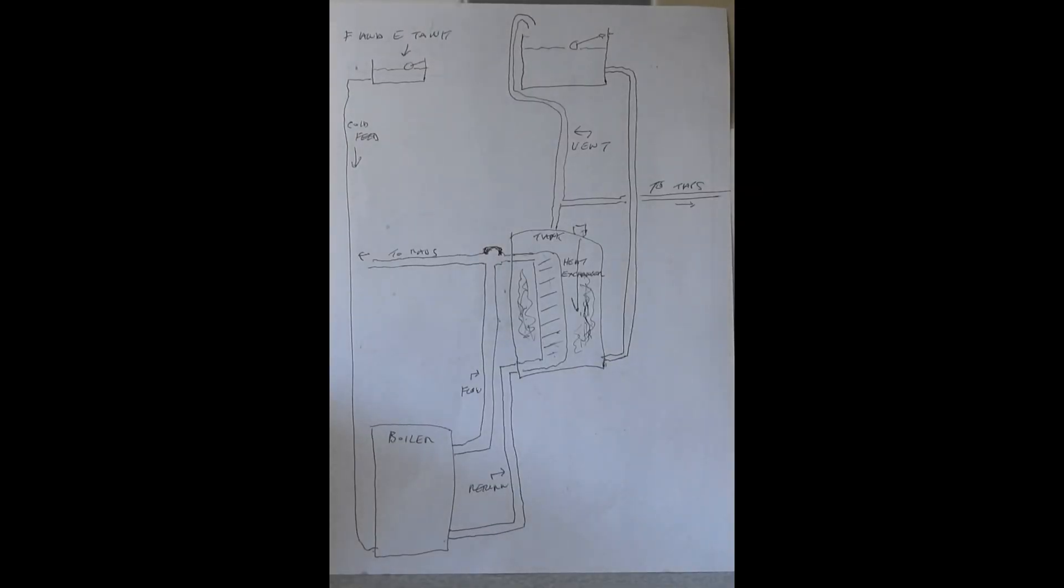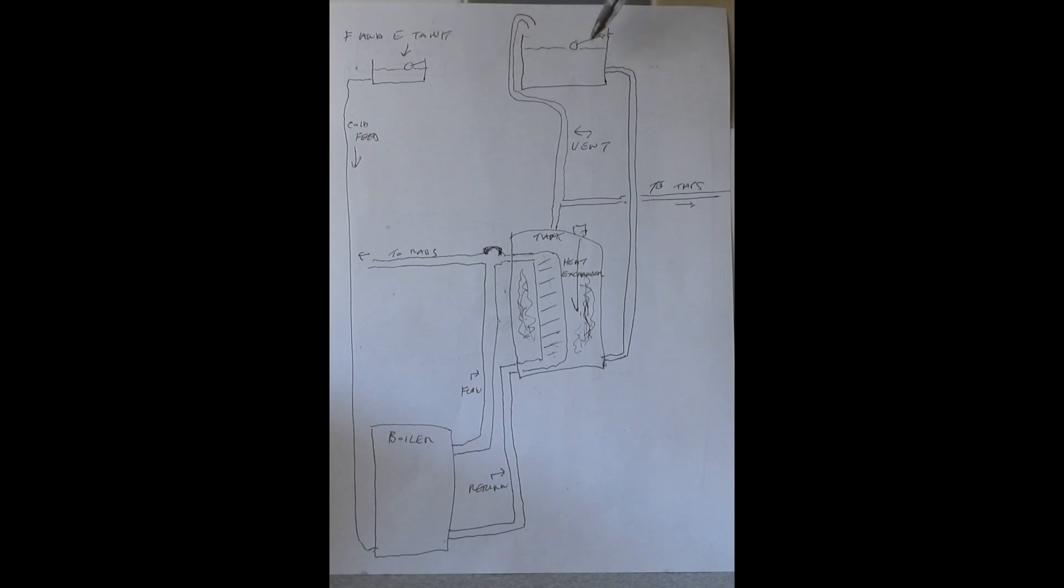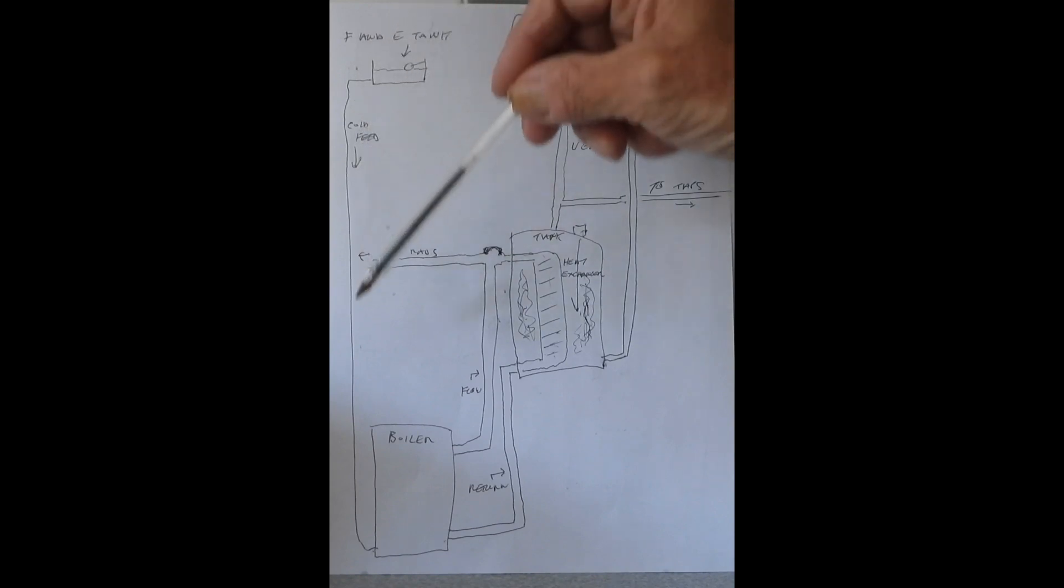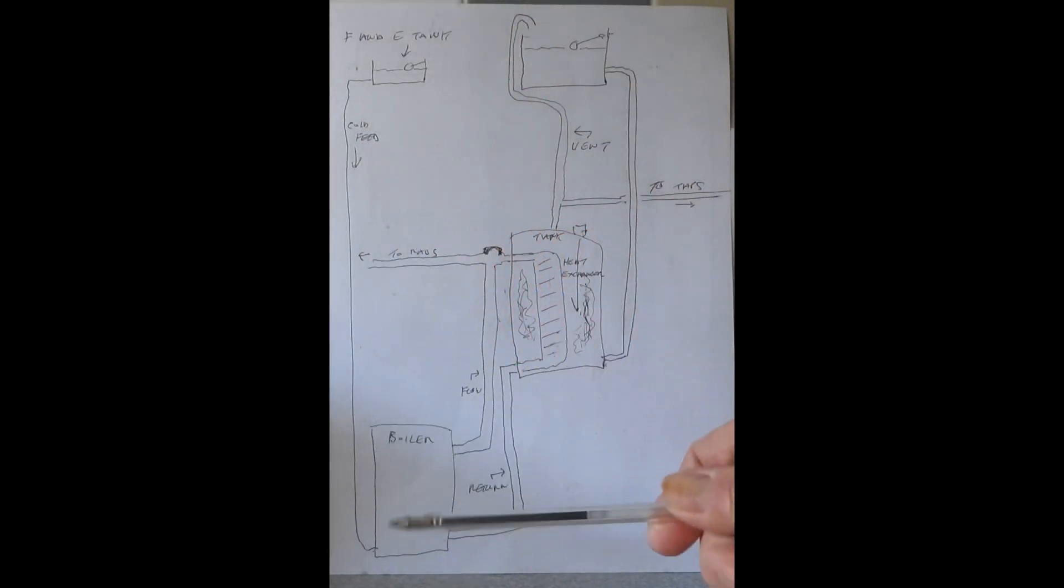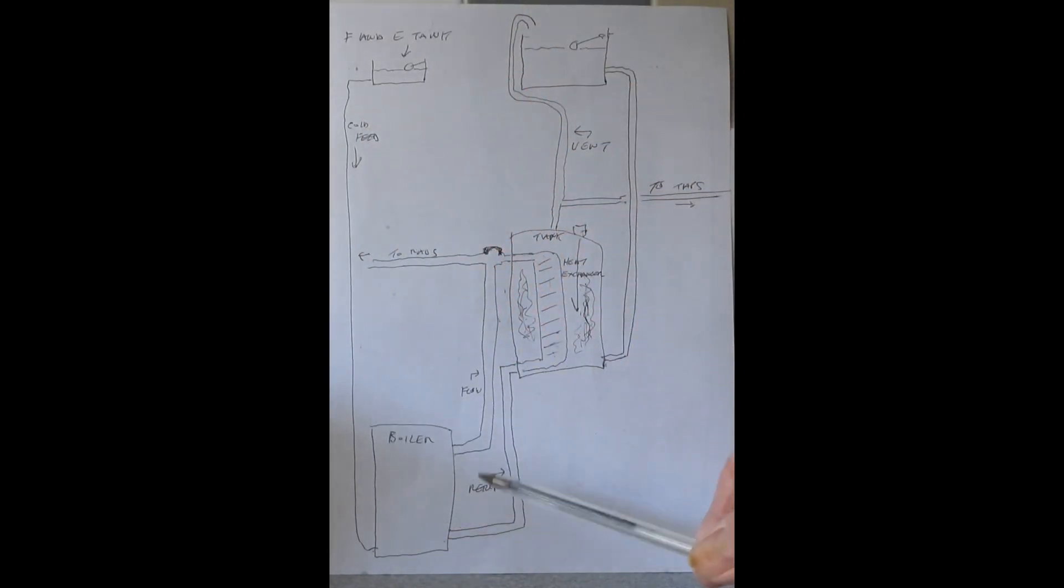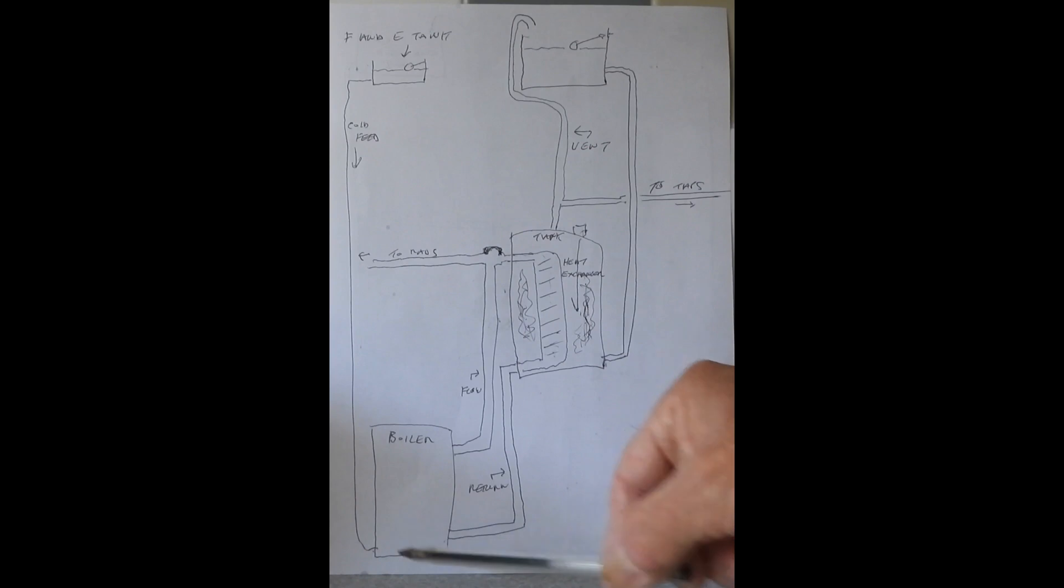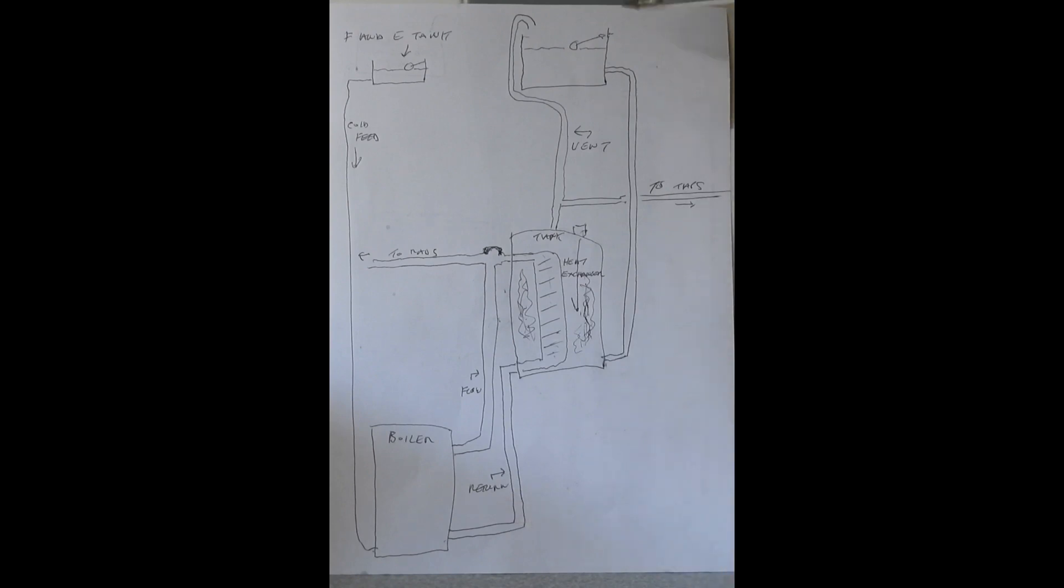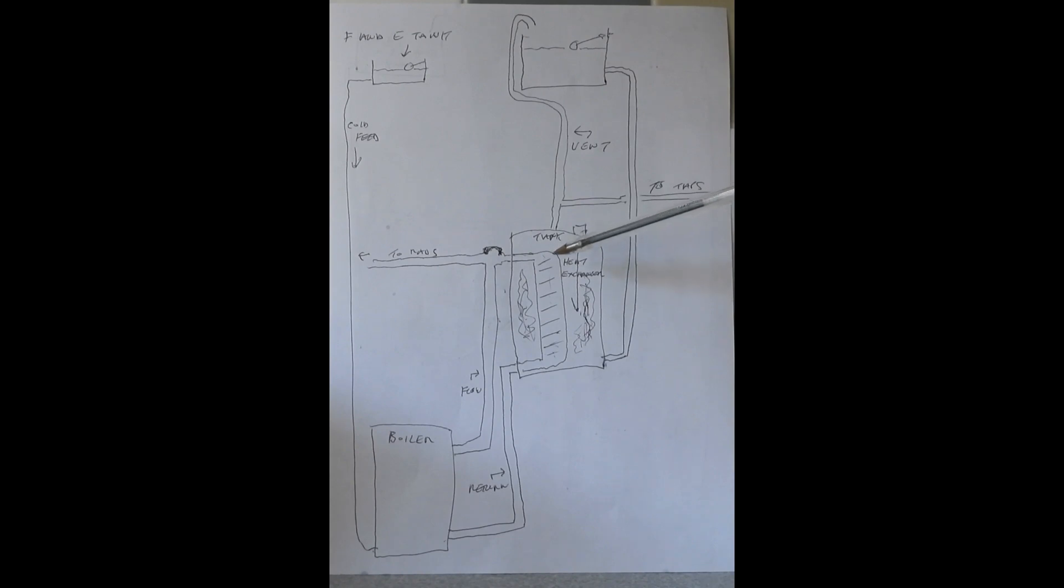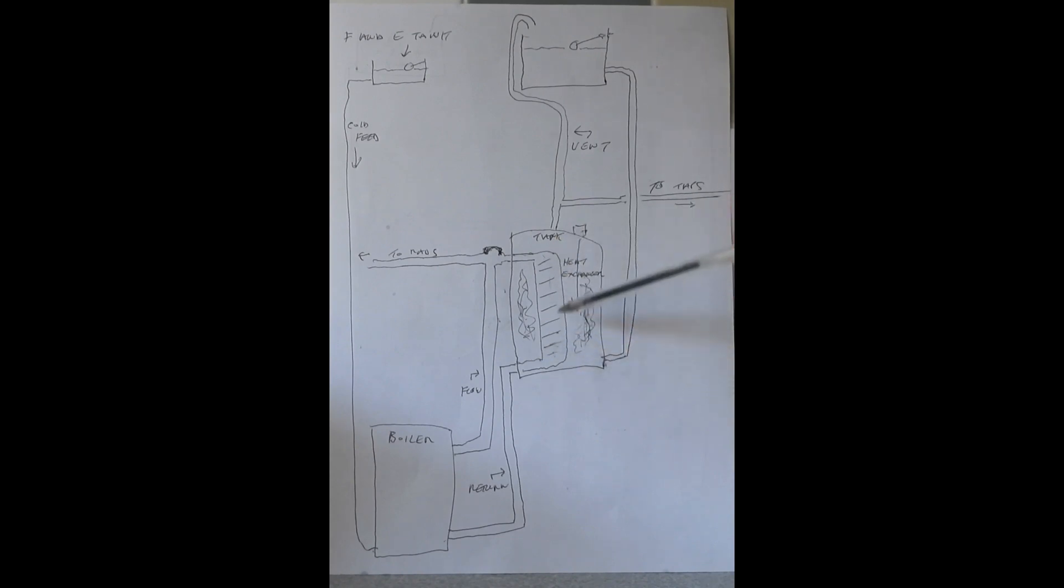Here we have the drawing with the amendments done. And the first one, an F and E tank up in the loft. It's got a little ball cock in it like your main one and it feeds into this tank. The water comes down, what we call the cold feed, and into your heating circuit. In this instance, I'll put it going into the boiler, but usually it'll go into the return somewhere and feeds the system. But you're thinking, well, why can't this one do it? Surely that one feeds it, doesn't it? And that's where you can see the difference in this new drawing. This most important part here called the heat exchanger.